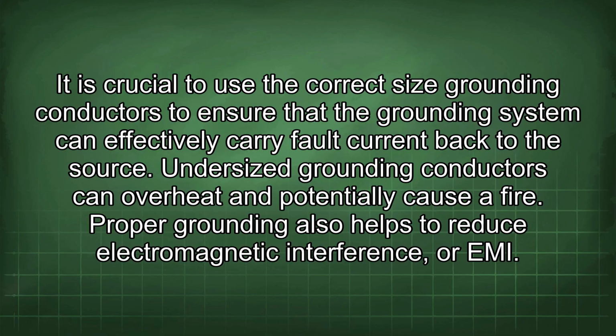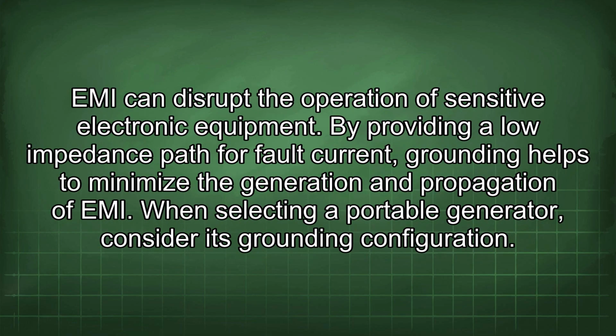Undersized grounding conductors can overheat and potentially cause a fire. Proper grounding also helps to reduce electromagnetic interference, or EMI. EMI can disrupt the operation of sensitive electronic equipment. By providing a low impedance path for fault current, grounding helps to minimize the generation and propagation of EMI.